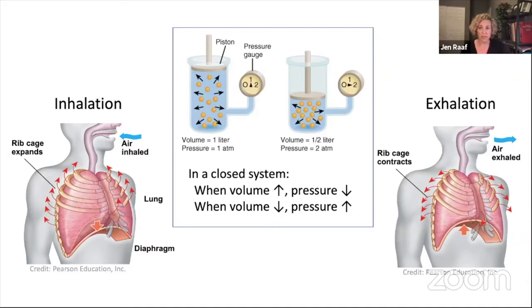In that case, sometimes a mechanical ventilator is necessary. What it's doing is creating a pressure differential to make air move into and out of your lungs. That's the main function of the ventilator we've designed, to create these pressure differences to make the patient inhale or exhale.